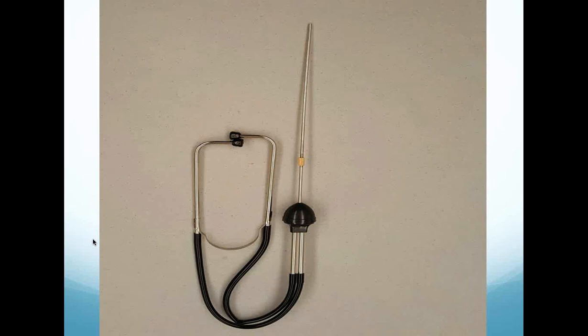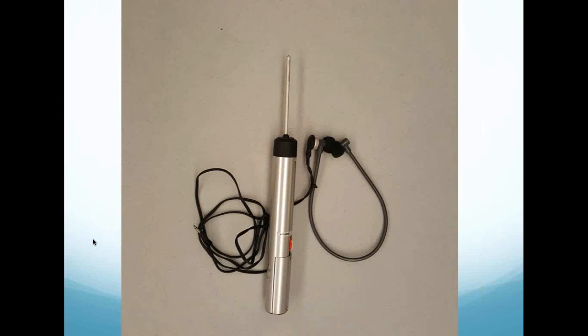You place these on the discharge side of an inverted bucket steam trap. You can put them on a floating thermostatic. You're going to hear different things. If you take an ultrasonic, this is a 20-year-old ultrasonic device, you place this on a floating thermostatic steam trap, and let's say you're up to temperature. The thermostat will be closed in that F&T body, but you will hear an actual velocity across that float orifice. So you will hear the discharging of the condensate. That's what you're going to be listening for.